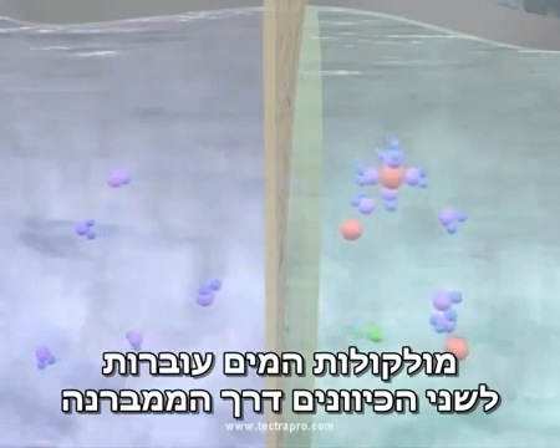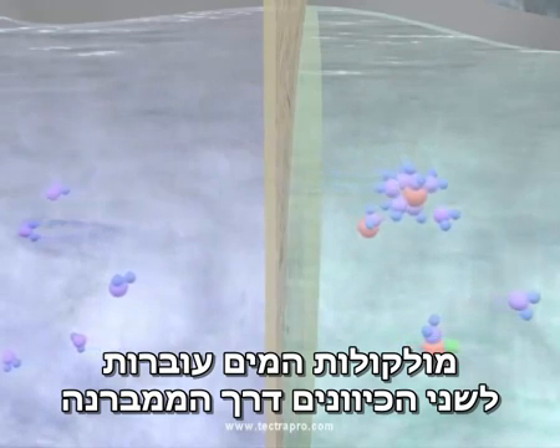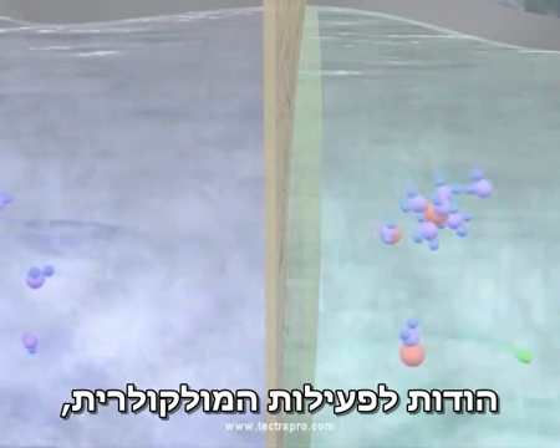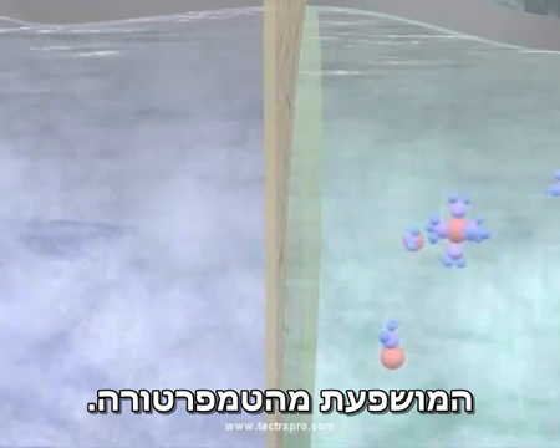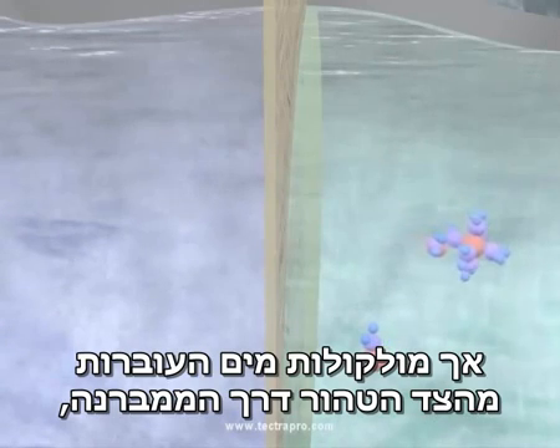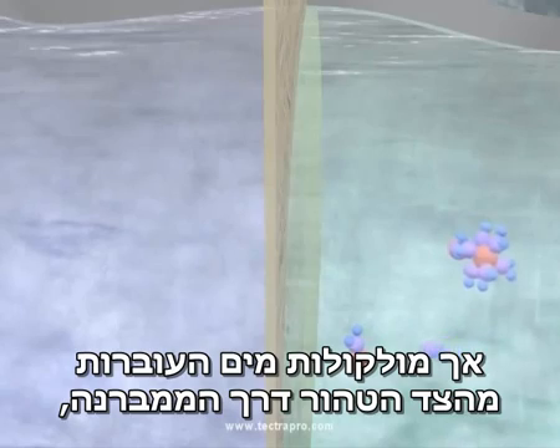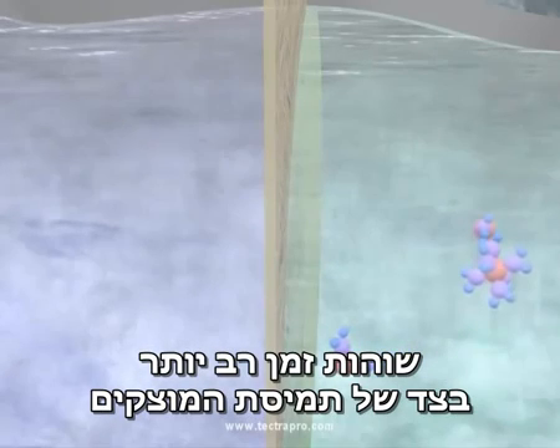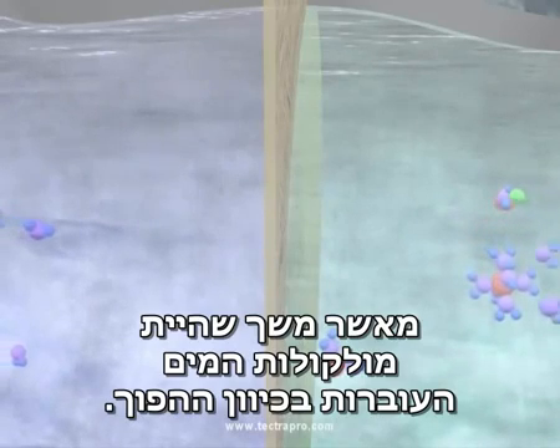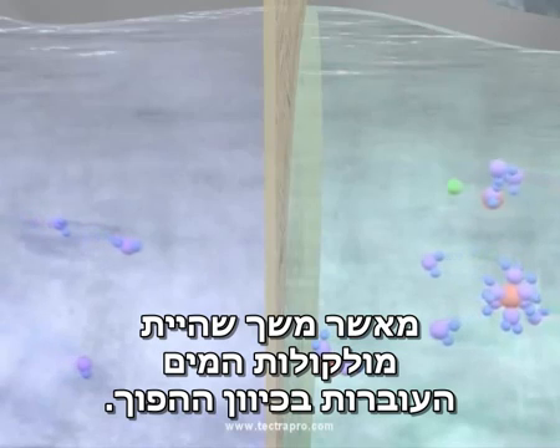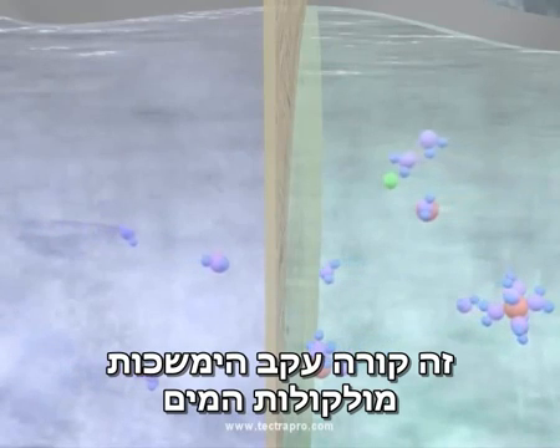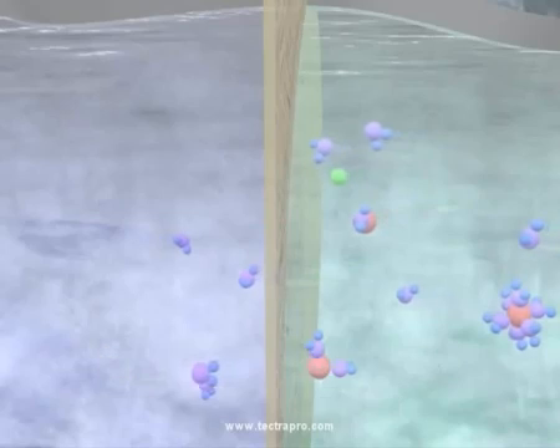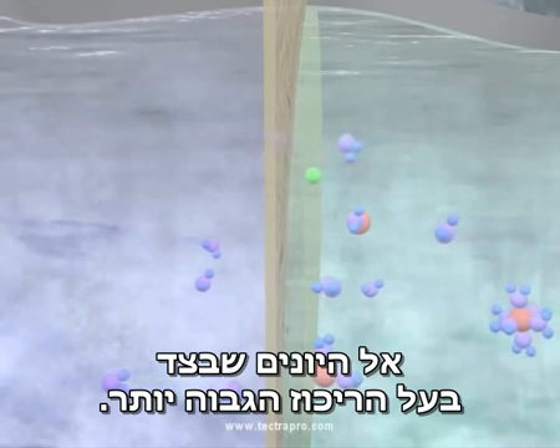Actually, water molecules travel in both directions across the membrane due to molecular activity, which is influenced by temperature, but water molecules that travel from the pure side through the membrane spend more time on the dissolved solid side than do water molecules traveling the opposite direction. This occurs due to the attraction of the water molecules to the ions on the higher concentration side.